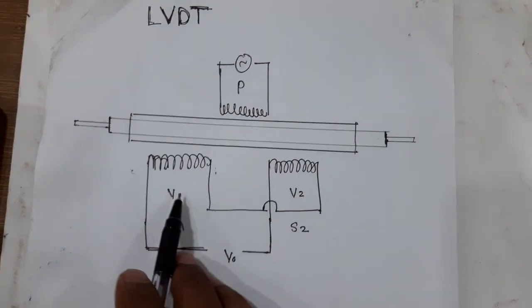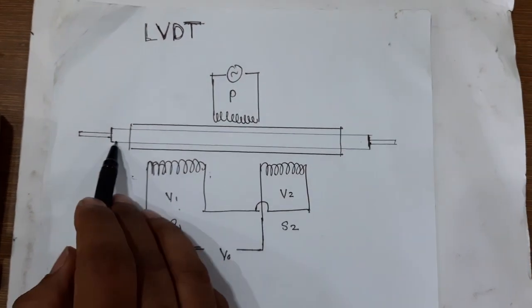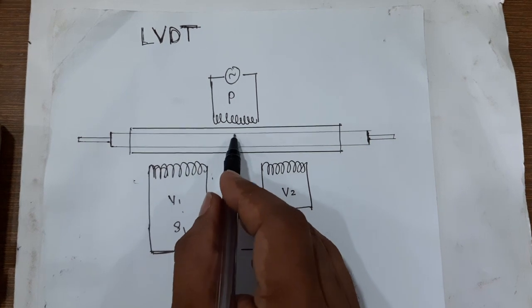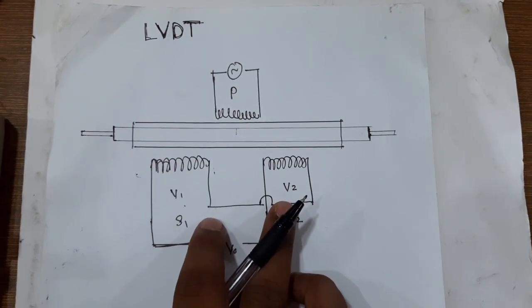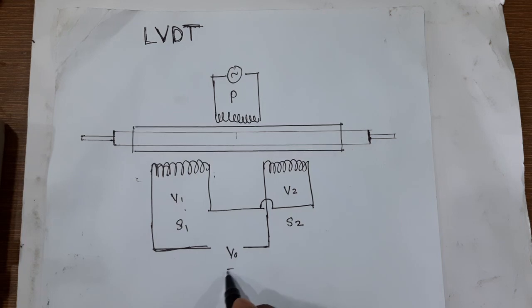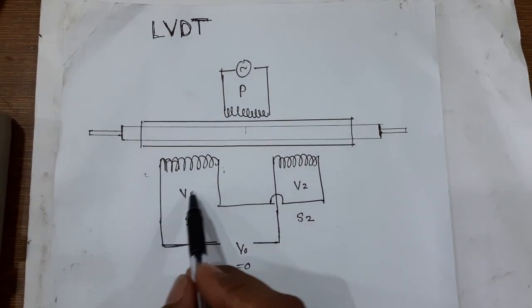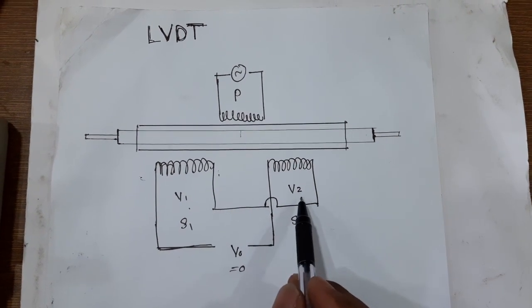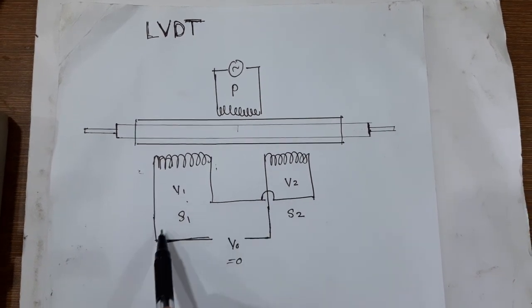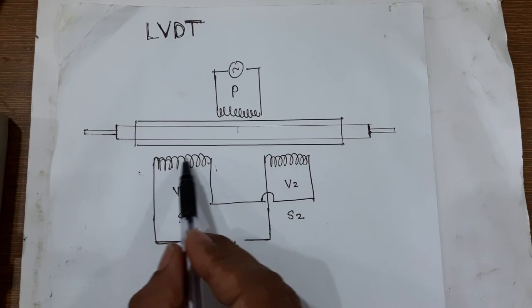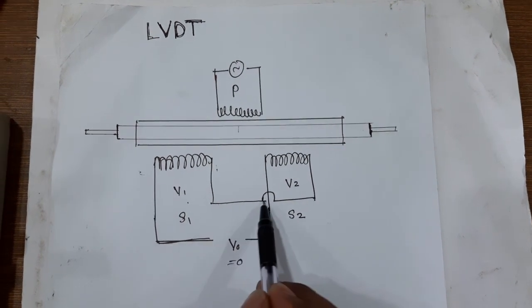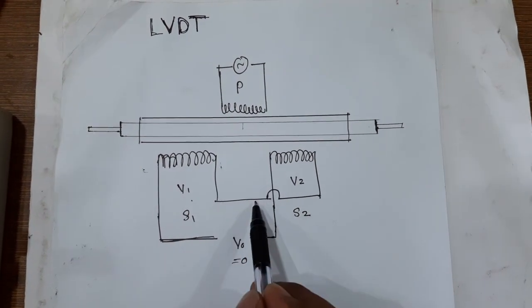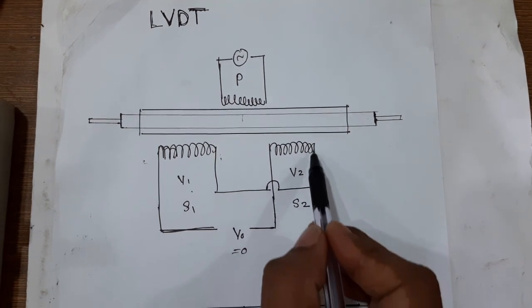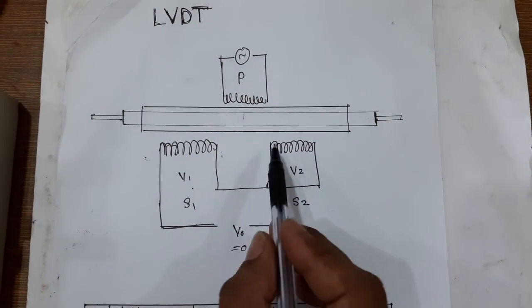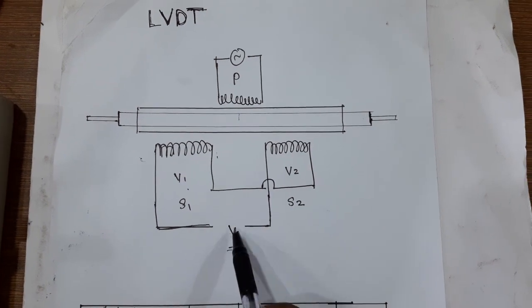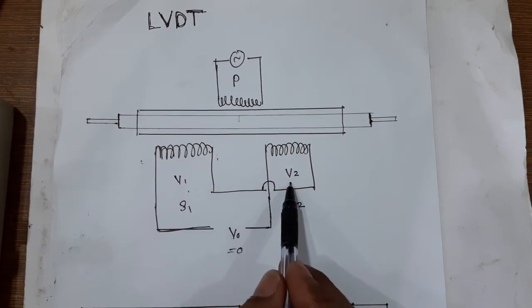So there are two outputs, secondary 1 and secondary 2. If this core is exactly at the center of both windings, the output is always going to be 0. Why? Because the output windings of both secondaries are connected in an opposite manner. The output from secondary 1 doesn't connect directly here, but goes to the end of the secondary and connects, and the output is taken from the opposite side. That's why the output is always the difference of V1 and V2.